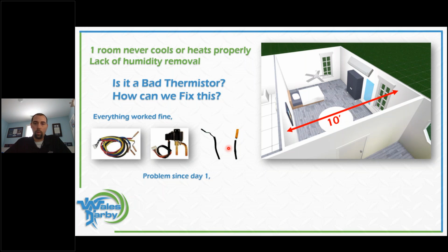And typically it's going to be in a room like this where we got a 10-foot wall in front of that indoor unit, right? So the biggest problem with this is we blow that air. These are powerful units. The 7 and 9s not as far, but when we get into 12s, it might throw air 29, 30 feet away, right? So I got a wall that's 10 feet long. That air is going to come out, hit that wall, bounce right back to the top.